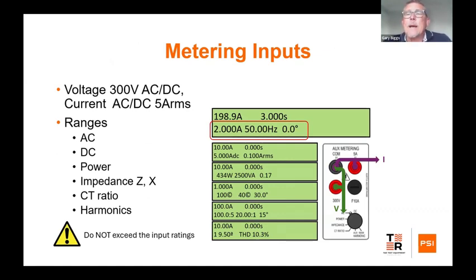We have also a meter built into our test sets. So we have auxiliary metering, and it's effectively like having a digital multimeter built into the test set. Again, back in the day when I first started, I would rock up with a variac and a transformer and a multimeter, and that's how I would do my relay testing. And obviously using a stopwatch, we would measure the time it took to trip a relay. In modern times, relays trip much faster, so the stopwatch is now out of the question. Having a meter built into the test set so that we can meter whatever we need to in respect to that relay, depending on what we're testing, is a big advantage. So as you can see here, we do have the meter built in to the relay test set, and as I said, it effectively is just a digital multimeter.